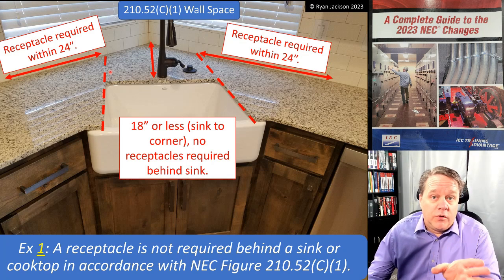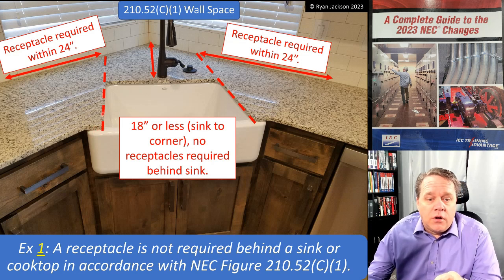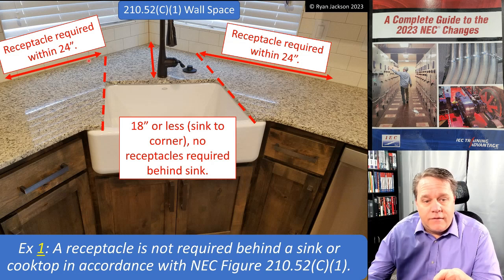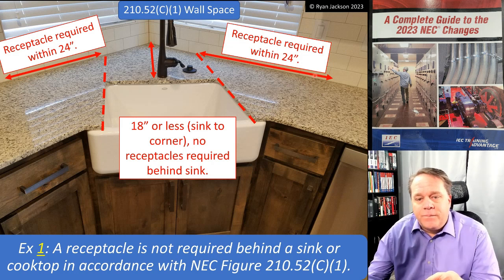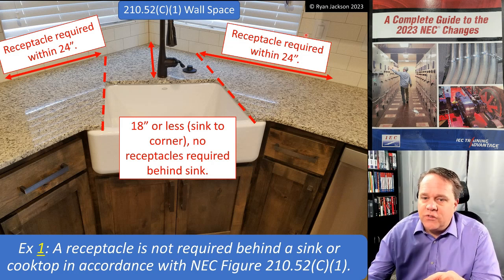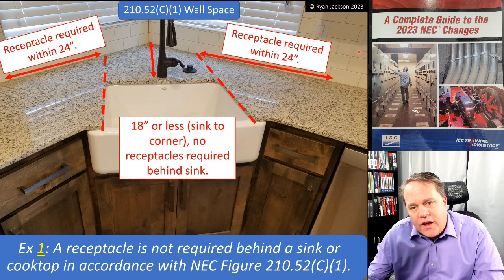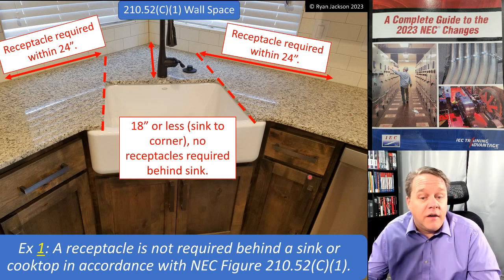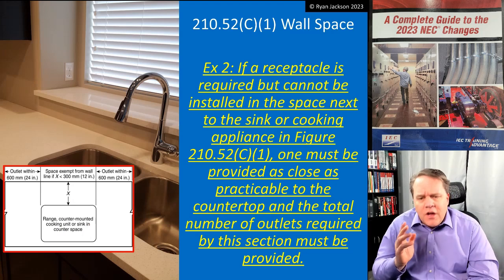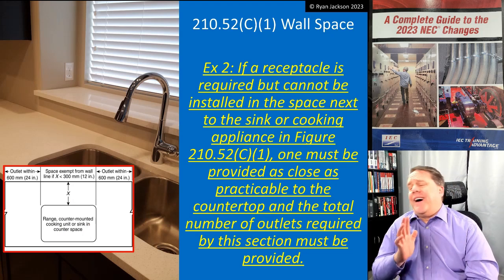A common mistake: when measuring for required receptacle placement around a sink, you need to draw an imaginary line along the sink and pull your tape back from there — a receptacle must be within two feet of that line. That often gets missed. Over on the right side, where the sink is, a receptacle nearby appears to be close enough.